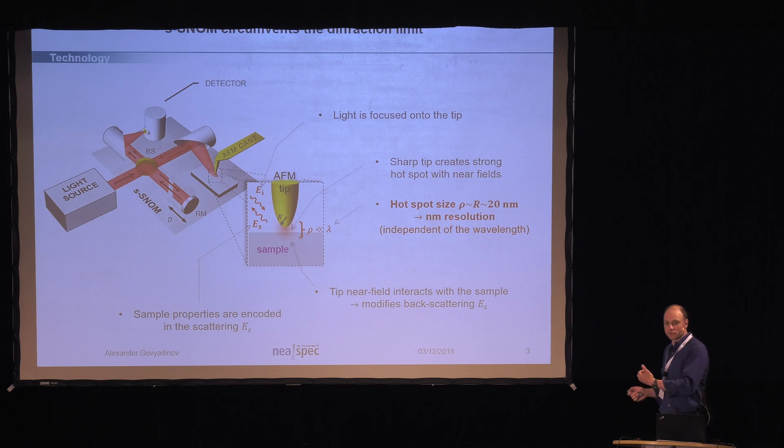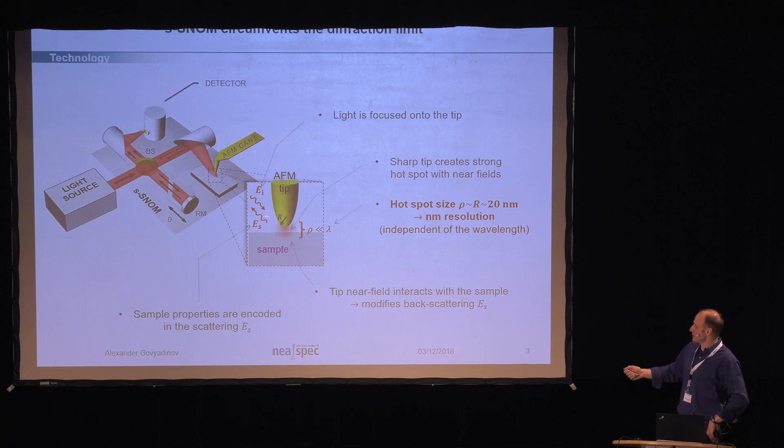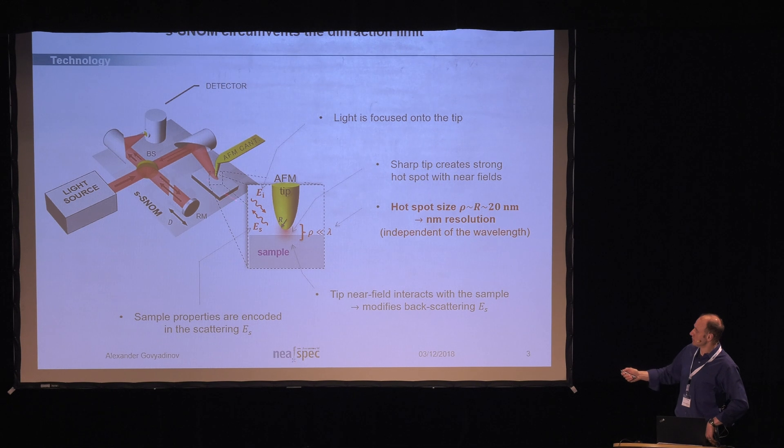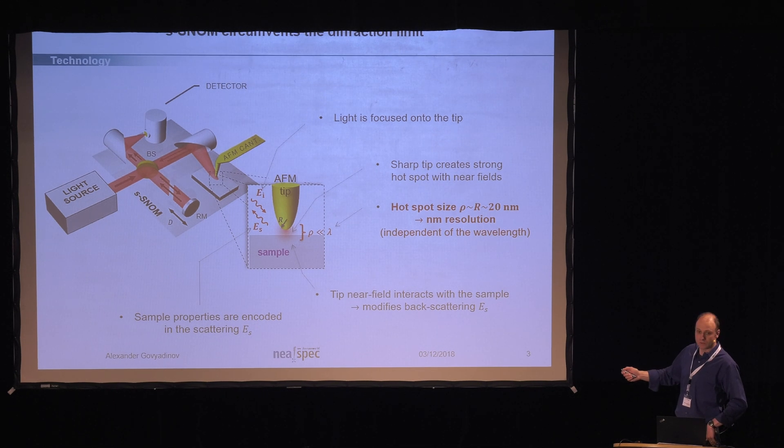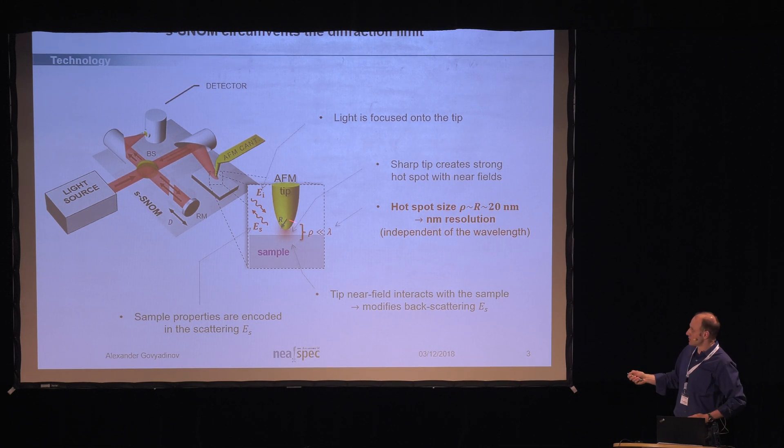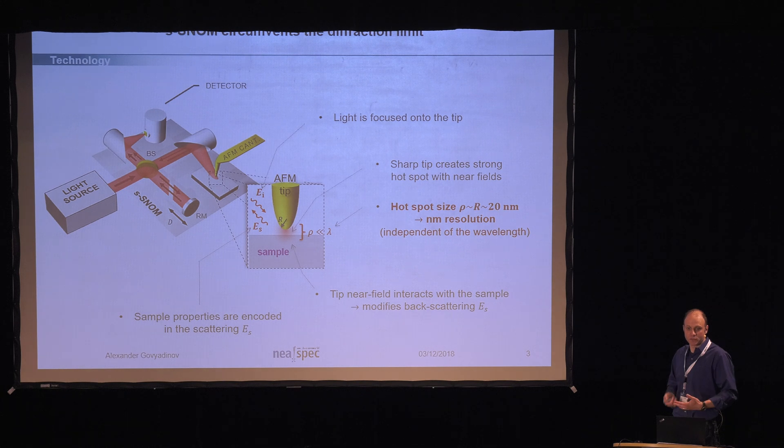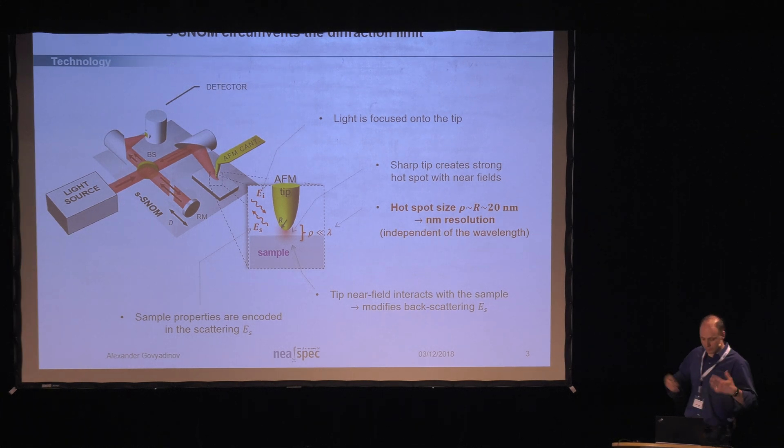This hot spot, because the tip is sharp, is very well localized to the scale of 20 nanometers. Essentially, it's on the localization scale of the tip radius. So this is actually the reason why neaSNOM is able to provide the nanoscale resolution. Now, what happens if you put the sample into this hot spot? The tip and the sample start interacting, electromagnetically, of course. And that modifies the backscattered light from the tip. So the tip captures the light, interacts with the sample, and then scatters back, and this scattering is detected at the detector. The scattering depends on what the sample is, what the properties of the sample are. And this is why the properties of the sample are encoded in the scatter signal. This is the basic principle.